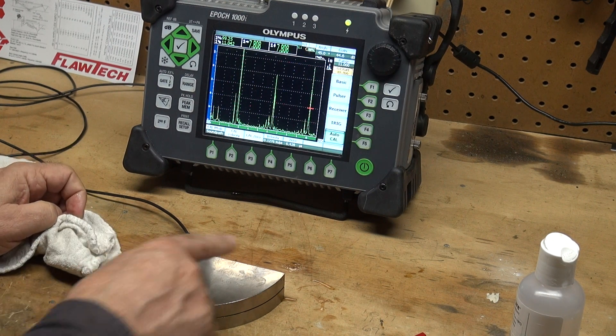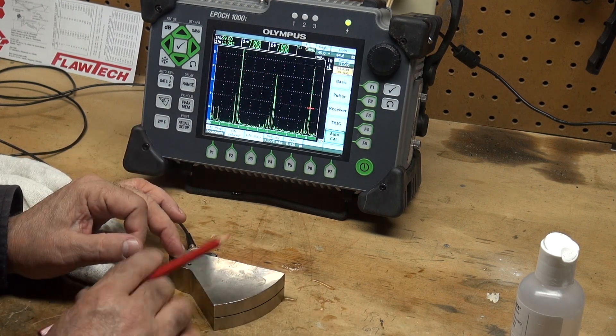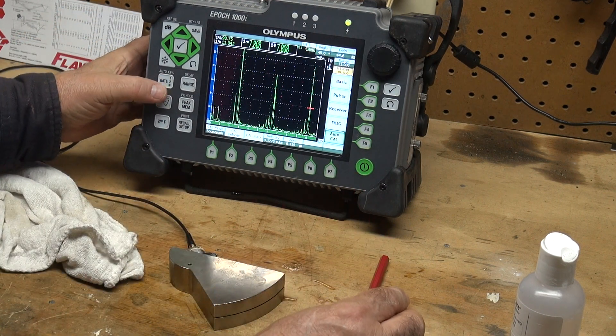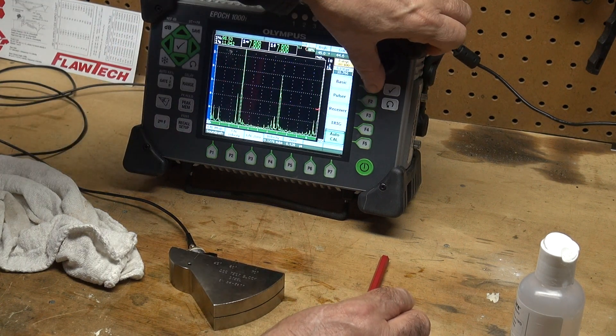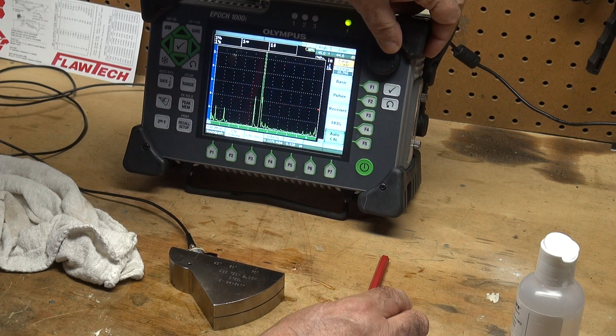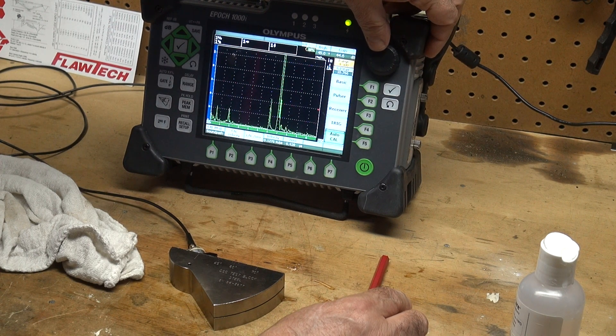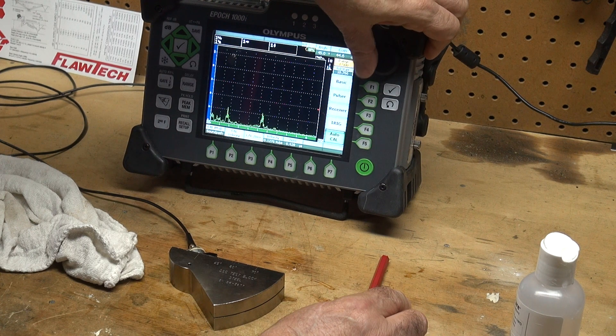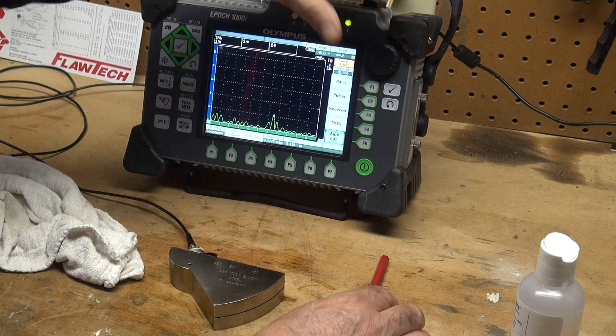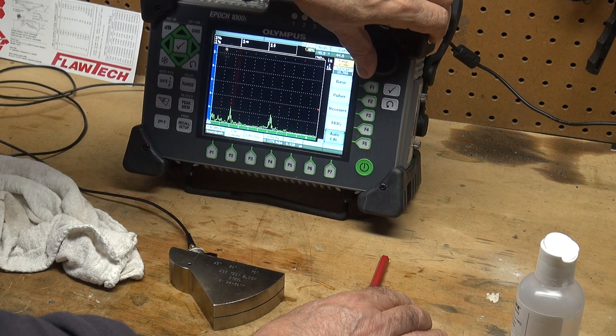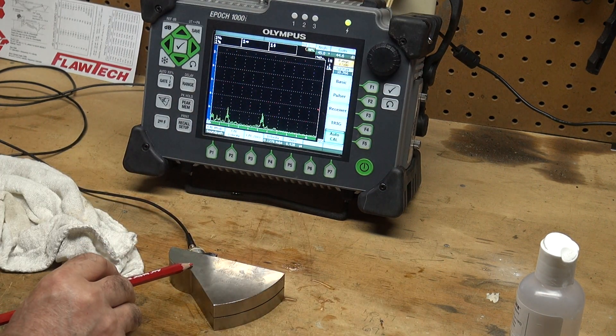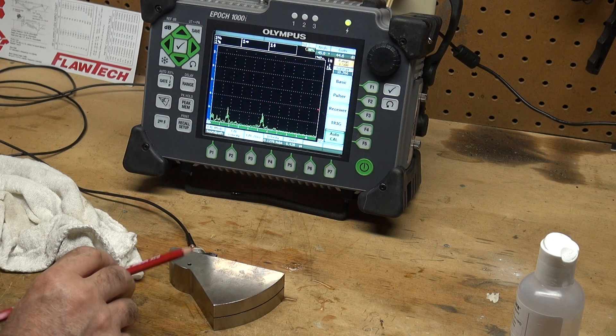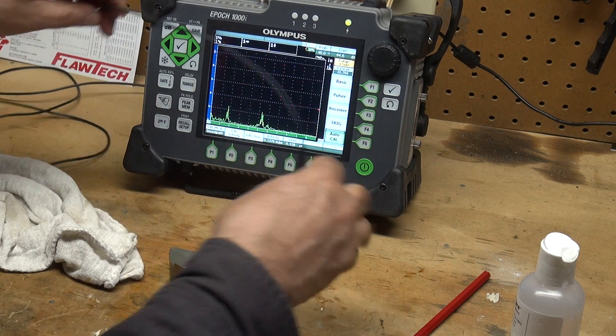So let's take a look. Let's measure, now that I'm calibrated, let's measure the angle of my transducer. So I'm going to take my range down to something more manageable, let's take it down to inch and a half. What we have here is we have a side drill hole and that is an eighth of an inch diameter. So to measure my angle...